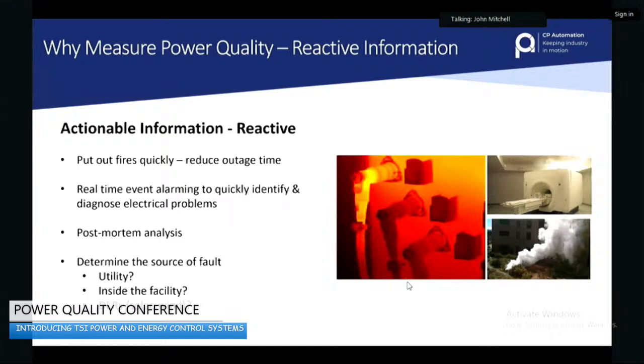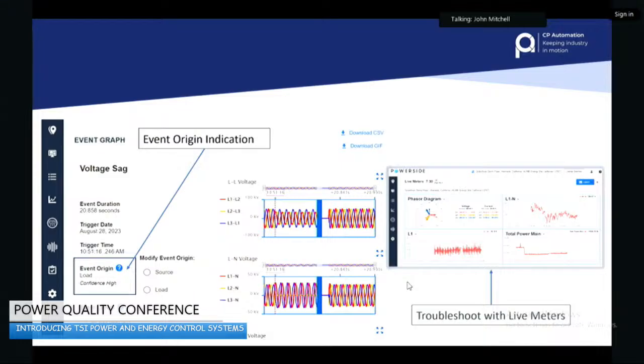Maybe they can get the data and go, okay, there's nothing we can do about that, we had a grid switching transient. We'll put a SineTamer in, that'll go away, and we don't have to spend half a day or a week investigating why all the equipment blew up. It doesn't even have to be equipment blowing up, it could be misfunctioning without them even being aware. Maybe the operational efficiency of a production line, say for a beverage company, could have a lower OEE that week just because of all these transients messing up the I/O.